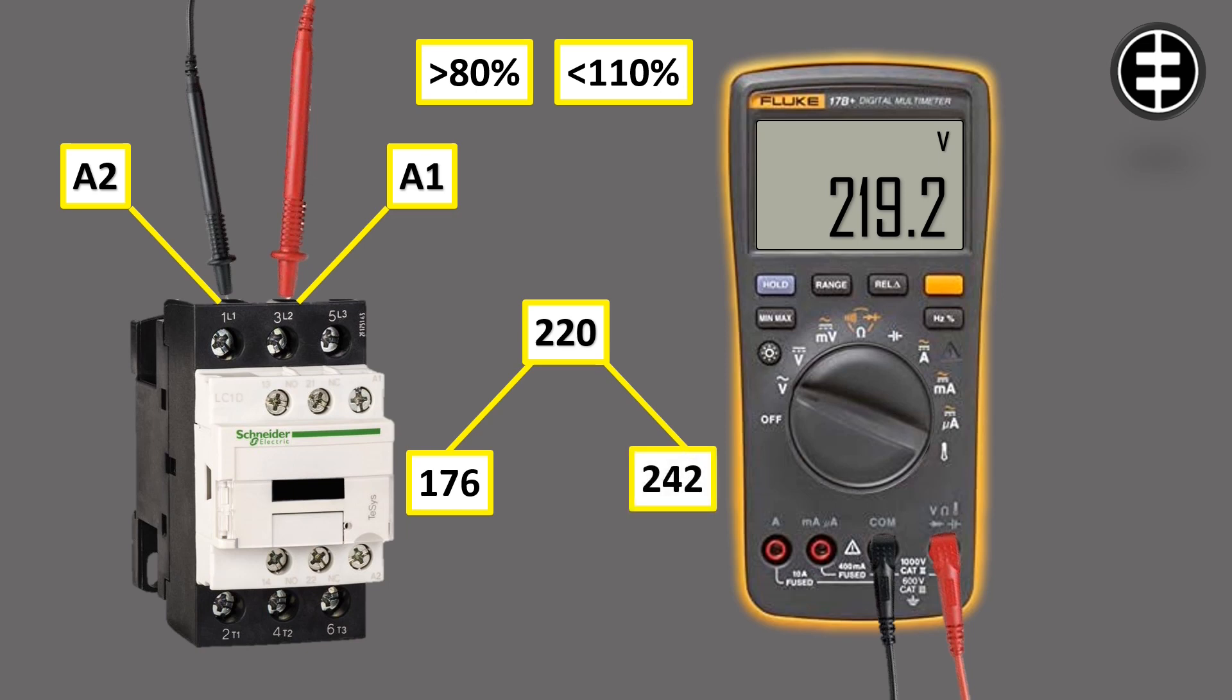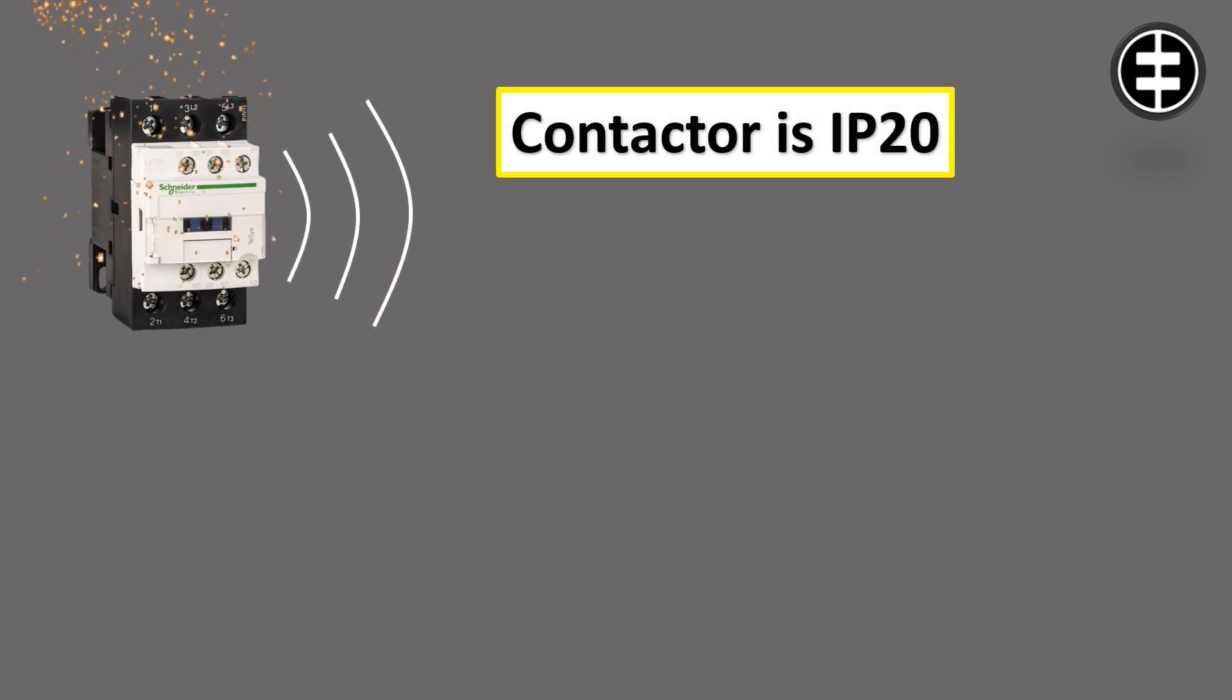Contactors, if used in a dusty environment, are at risk of dust deposition on the core and armature. Dust can also generate noise during contactor power-up time. The contactors' IP rating is normally 20, which protects from objects bigger than 12.5 millimeters, but dust particles are smaller than 1 millimeter.